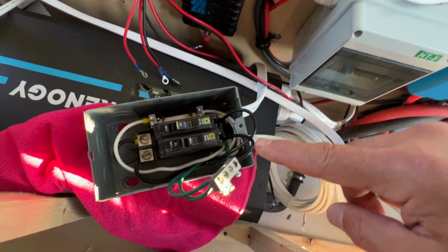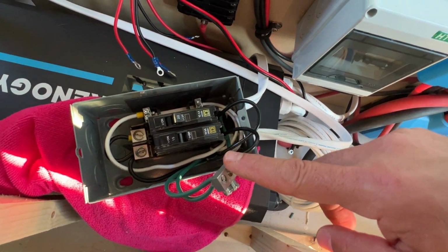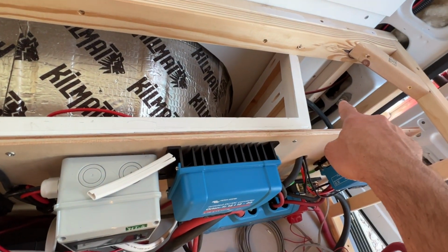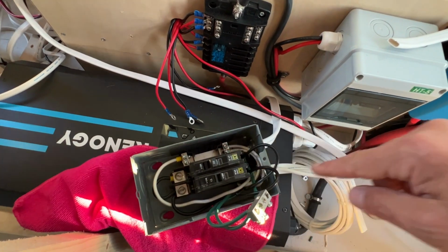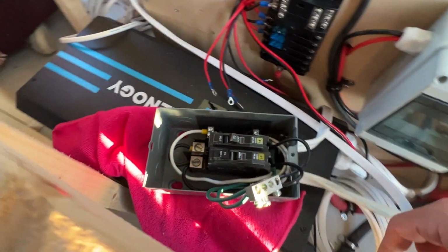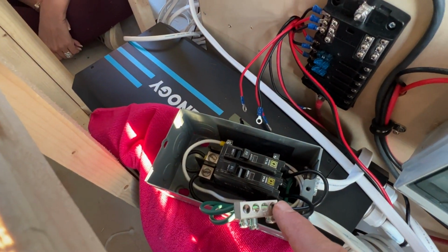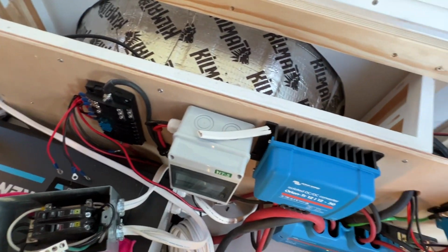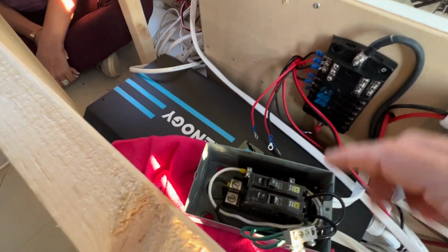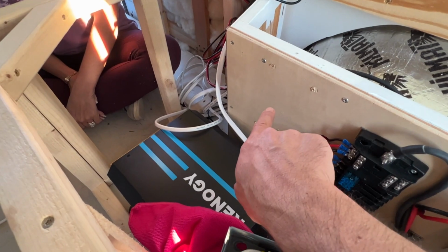What I'm going to do is get my ohm meter working, and I'll put one here and one there, and if they show no resistance, then I know this is already grounded through the inverter and we don't need an extra wire. If we do need a wire, we'll plug it into one of those, run it through here to that point, and then we will put a lid on this and stick it right here.